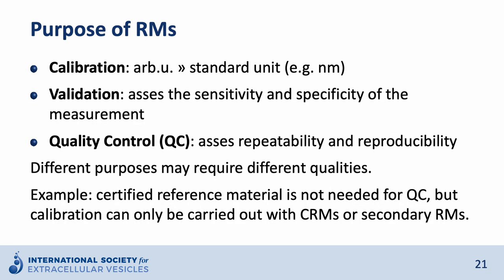Reference materials can serve different purposes. One purpose is calibration, converting measurement results from arbitrary units to standard units. Another purpose is validation, which means the assessment of the sensitivity and specificity of the measurement. A further purpose is quality control of an instrument or measurement assay, meaning the assessment of repeatability and reproducibility over time. It is important that different purposes may require different qualities — for example, a certified reference material is not needed for daily quality control, but calibration of an instrument can only be carried out with a certified or secondary reference material.